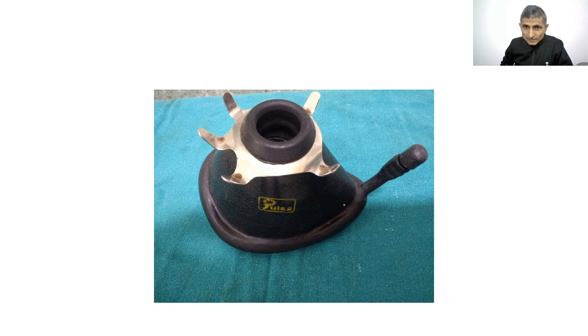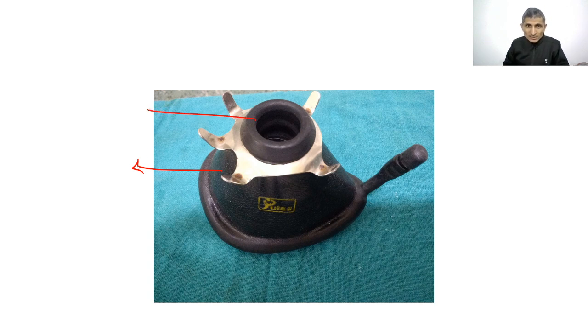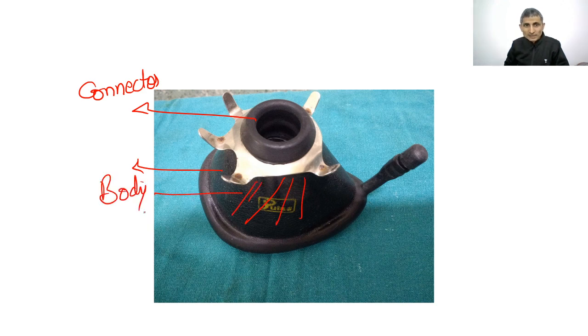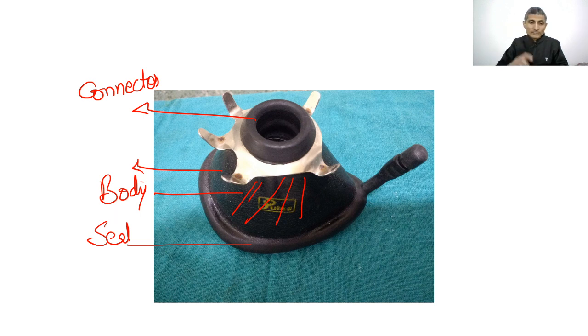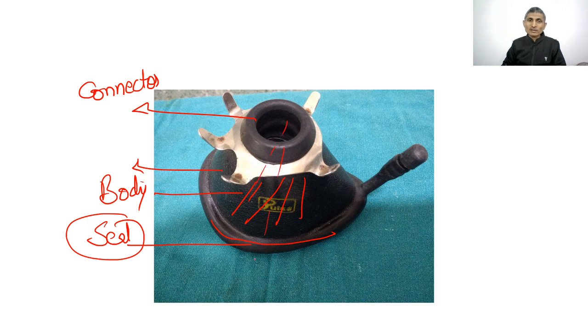This is an anatomical face mask used for adults. It has three parts: a connector that attaches to the breathing circuit, the main body, and the seal. When gases are delivered, the mask is applied over the mouth and nose; the seal forms a tight seal over the face to deliver gases to the patient.